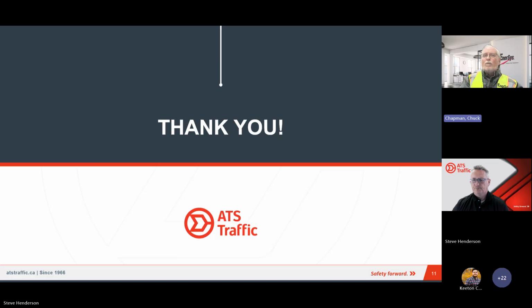Yeah, and I'd say, this is just a comment, for any non lead acid or nickel cadmium battery system, the primary programming in the FXM currently is around lead, right? There are temperature compensations or other things. I actually have a large background in energy sources that are not traffic. I'm NABCEP, North American Board of Certified Energy Practitioners, certified in PV and storage, and I work with SEAC also, the Sustainable Energy Action Committee. The only thing I can tell you is that most of these newer storage technologies do not require temperature compensation. That being said, the FXM has a setting in it for setting the temperature offset.